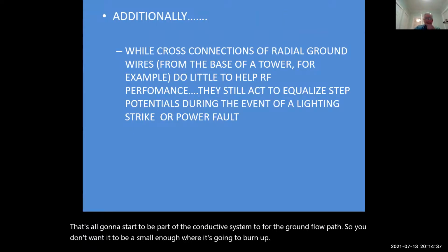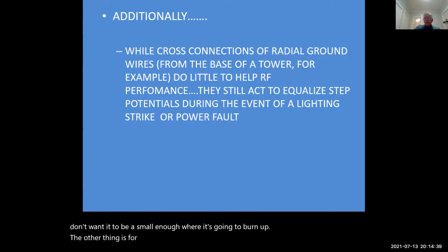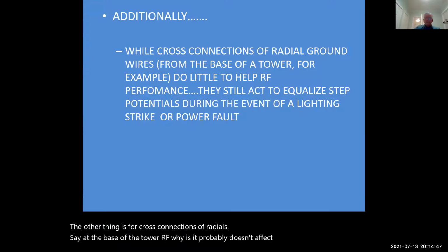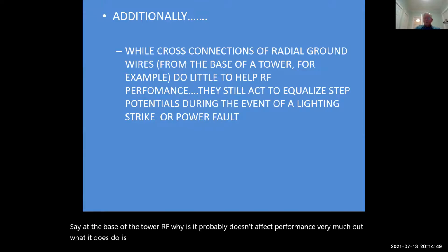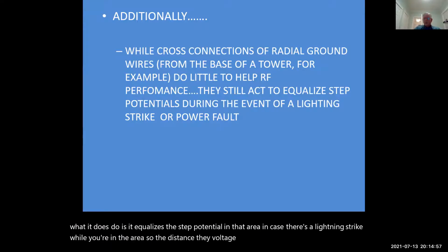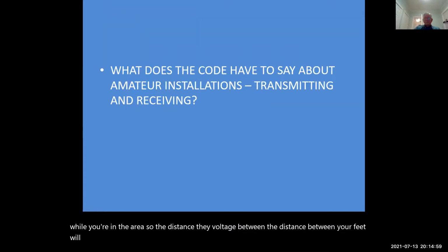The other thing is cross connections of radials, say at the base of a tower. RF wise, it probably doesn't affect performance very much, but what it does do is equalize the step potential in that area in case there's a lightning strike while you're in the area. So the voltage between your feet will be more tolerable.